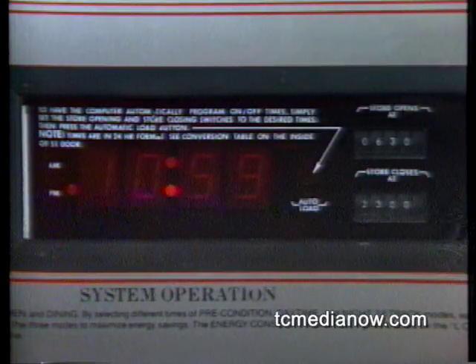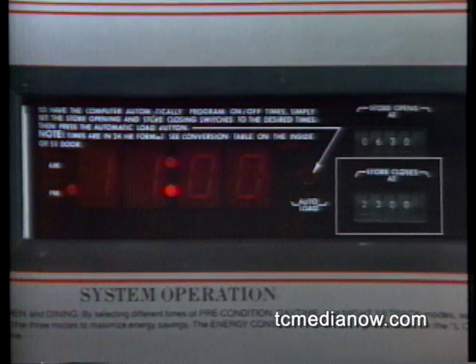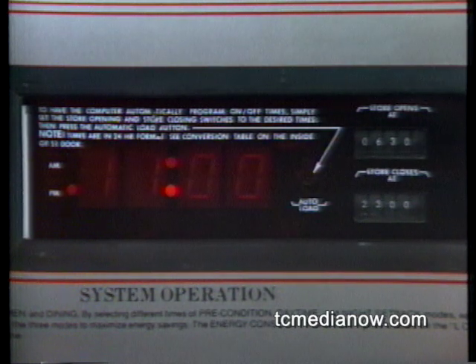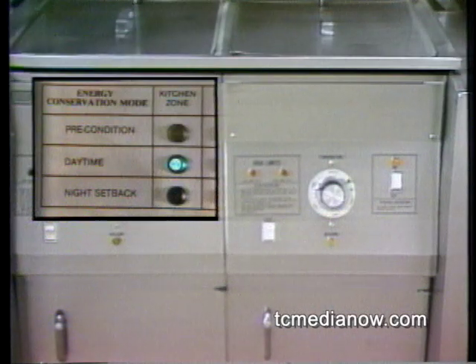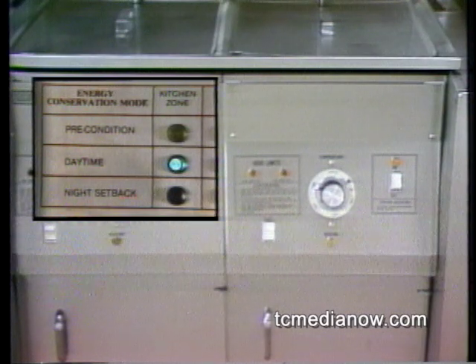When exterior lights are no longer needed, a photocell on the roof causes the system to turn them off. In the evening, when it begins to get dark again, the photocell automatically turns them back on. At the store's closing time, set on the second thumb wheel, the dining room is automatically placed into the night setback mode. In the kitchen, the fillet fryer acts as a system override, keeping the kitchen in daytime mode for as long as the fryer is kept on.